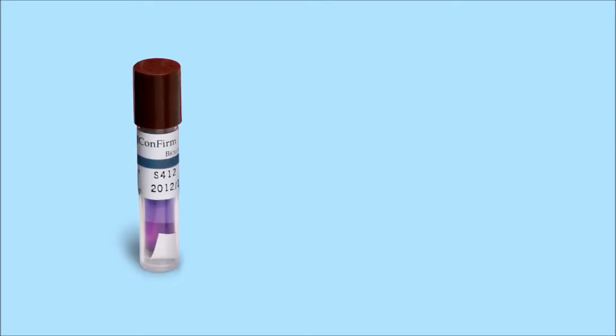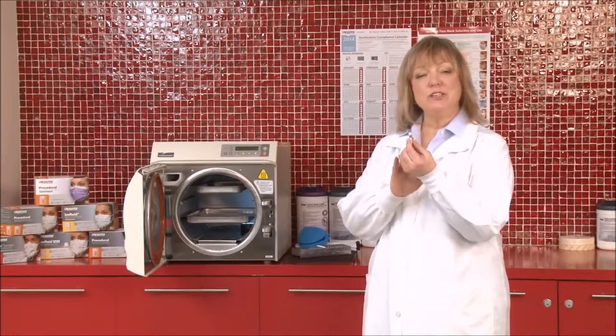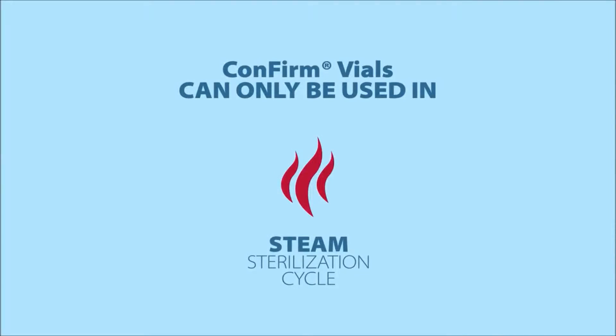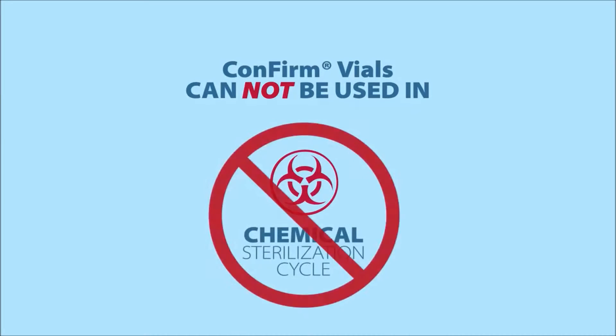The ConFirm in-office biological monitor can only be used in a steam sterilization cycle. This particular ConFirm product cannot be used in dry heat, cannot be used in a chemiclave cycle.